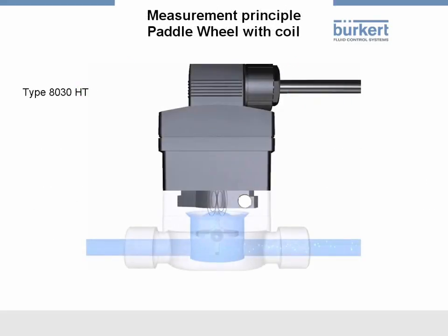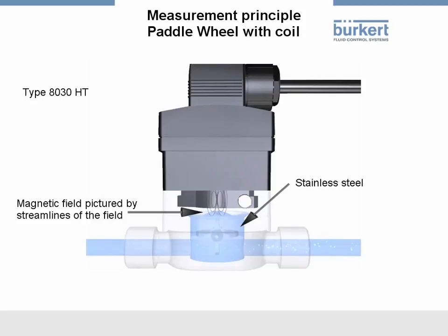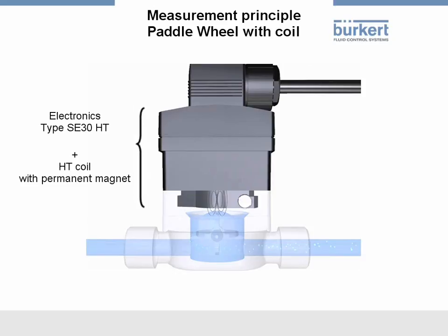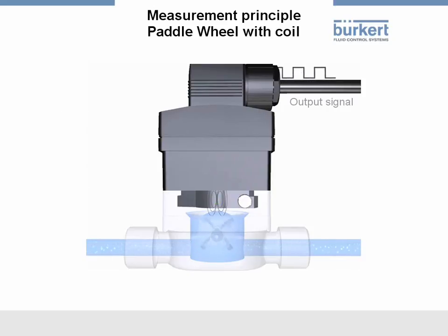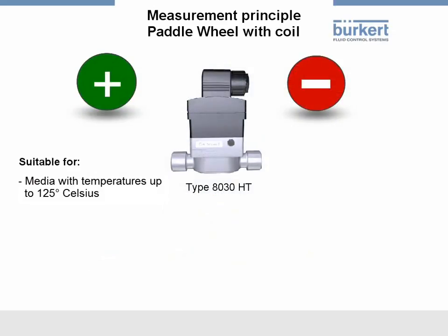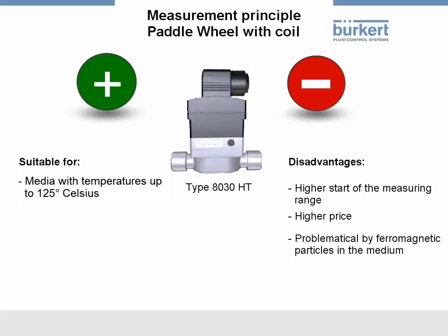In the next flow measurement principle, the paddle wheel is made of stainless steel. Due to the very low iron content, the paddle wheel is not magnetized. Outside of the medium area, in the electronics housing, there's a high-temperature coil with permanent magnets. The magnetic field of the coil opens or closes alternately due to the rotation of the paddle wheel. This produces a sinus-shaped frequency signal in the coil, which is converted by the electronics into a rectangular frequency signal. This method is used especially for media with temperatures up to 125 degrees Celsius. The disadvantage is the higher start of the measuring range and the higher price. Also, the presence of ferromagnetic particles in the medium rules out the use of this measuring principle.